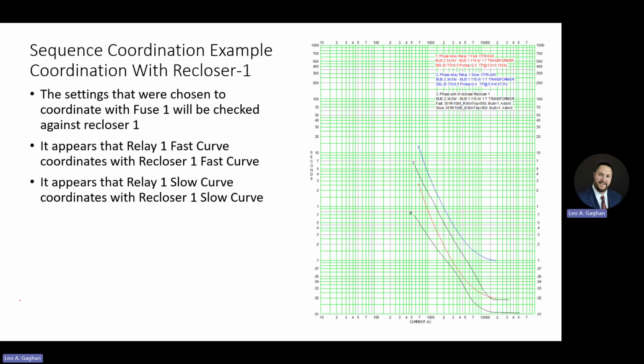coordination with recloser 1. We can see here that curves 1 and 2 are for the relay fast and slow curves, respectively. And then curves 3 and 3F would be the fast and slow curves, respectively, for the recloser. So it's kind of weird to show here, we've got two separate curves set up for the relay. But in Aspen, if you actually tell it it's a recloser controller, it automatically creates that F designation, like the 3 and the 3F, for you. So we can see that.